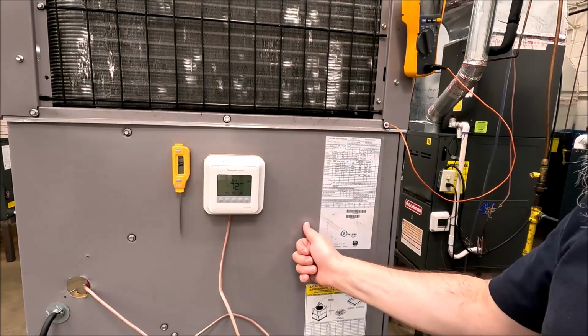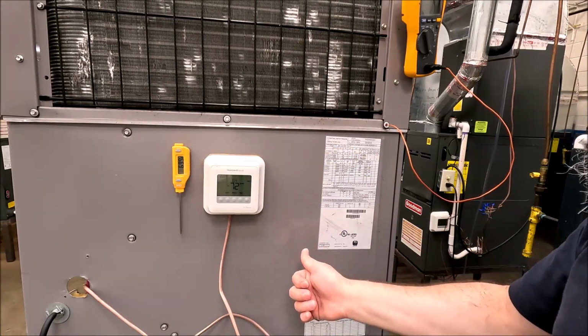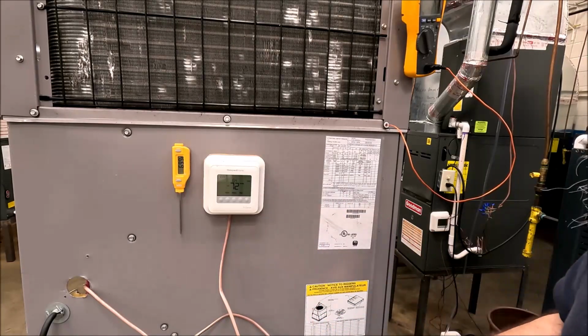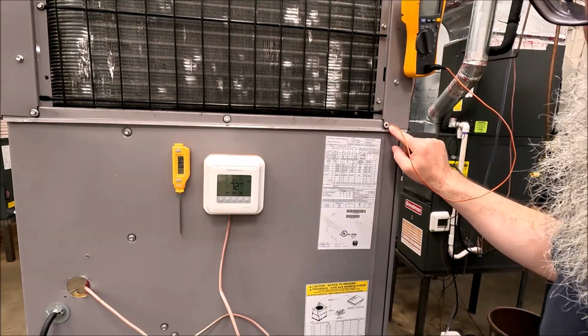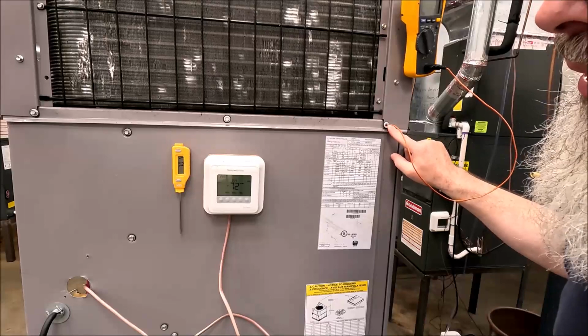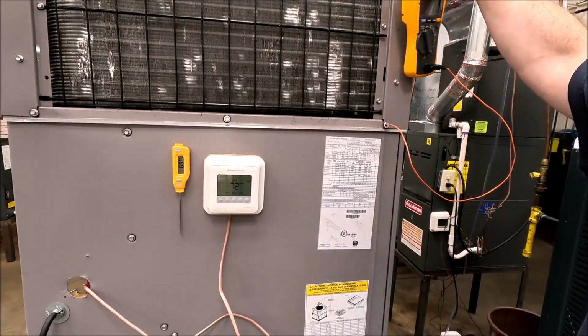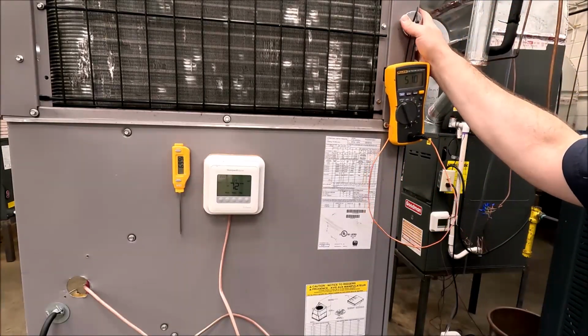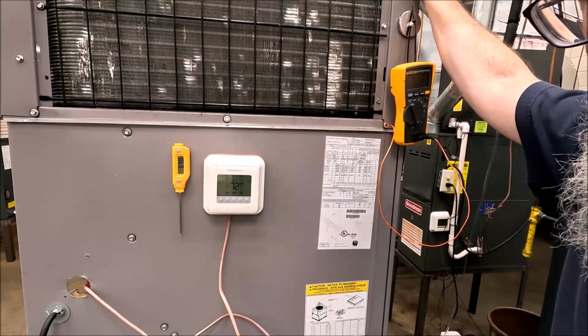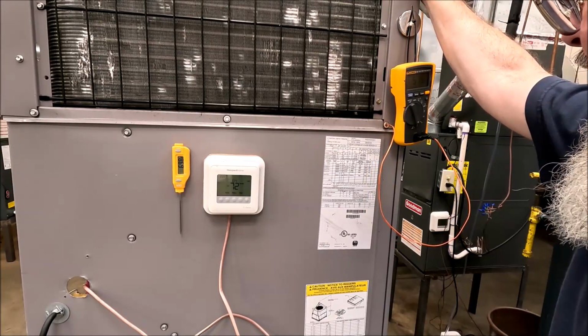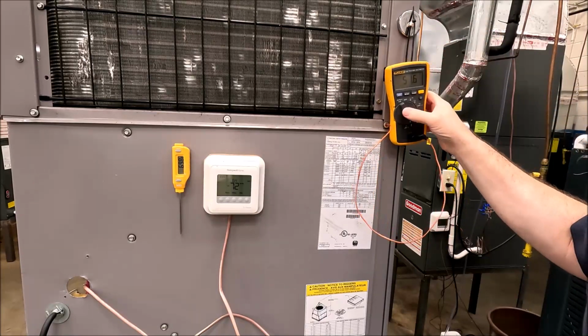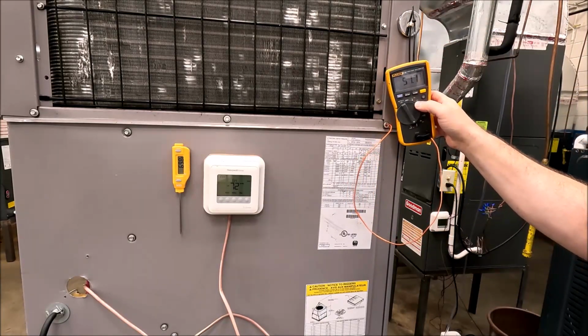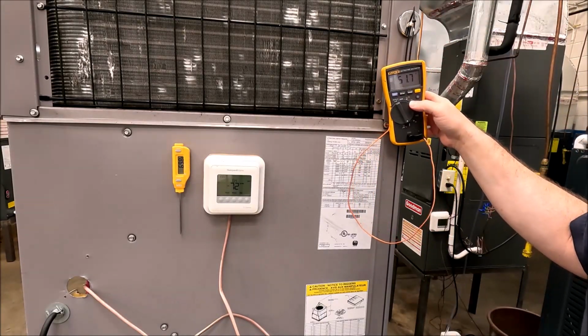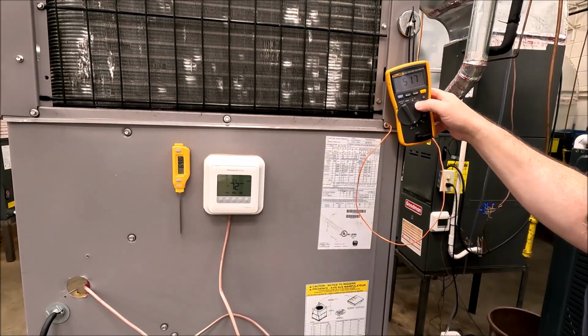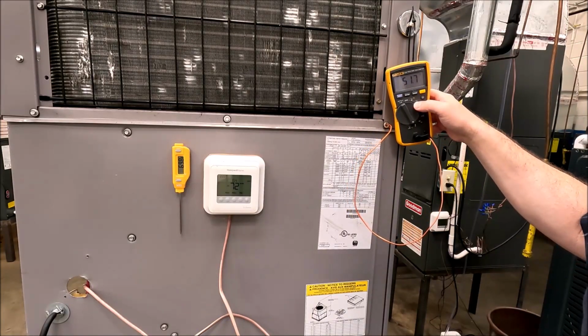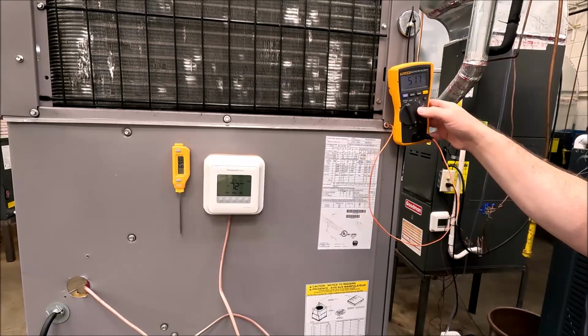So if you're going to do something crazy like that, at least make it look good somehow, some way. I'll leave that up to you, but the screw hole's already there. If it happens to work for you, it's good. And as we look here, I've got a 51.1 degree supply temperature. 51.7, it kind of bounces a little bit, right? Numbers move just ever so slightly. That's pretty good. 71 going back in, 51 coming out.